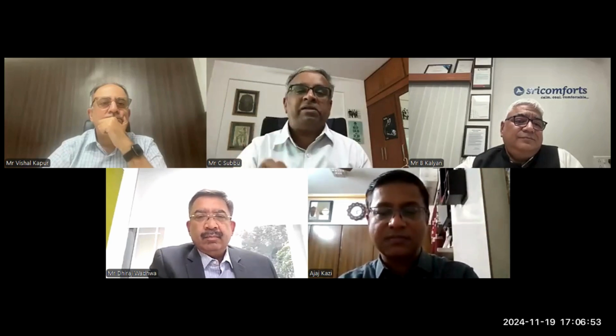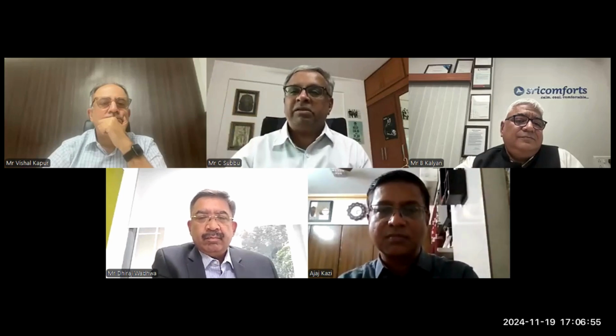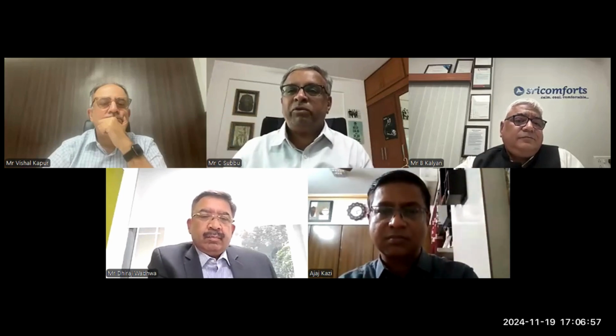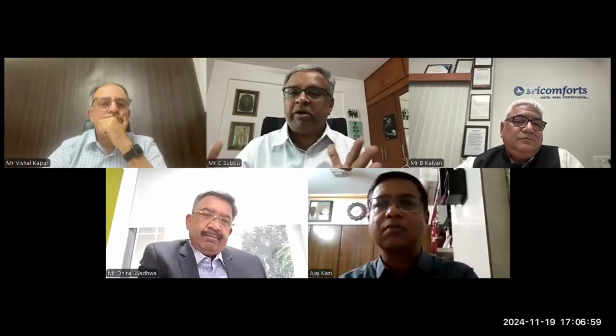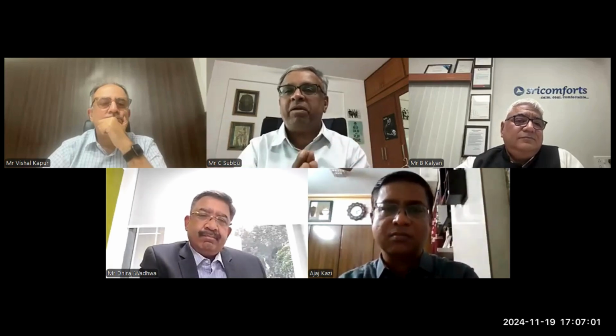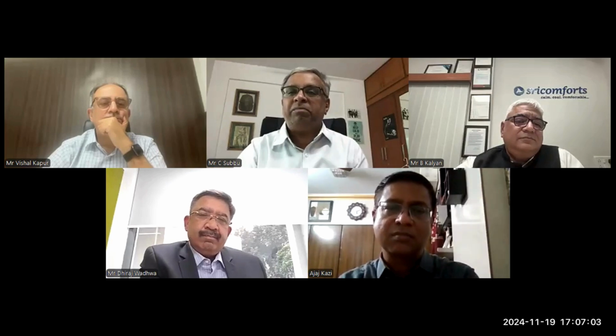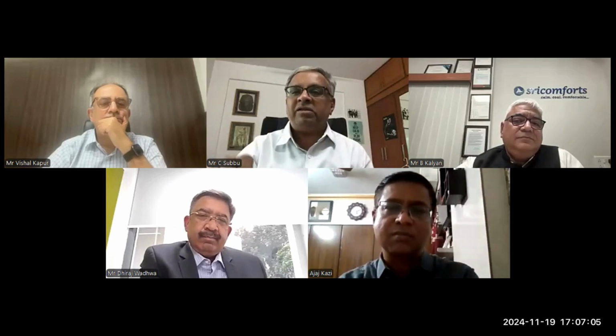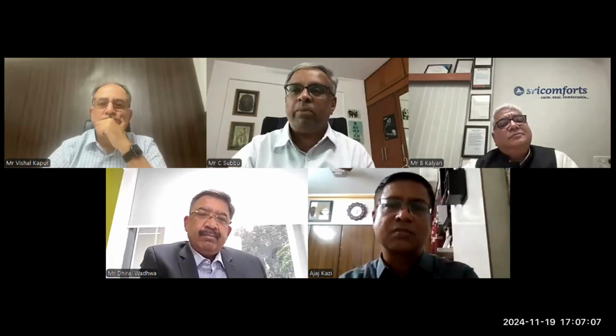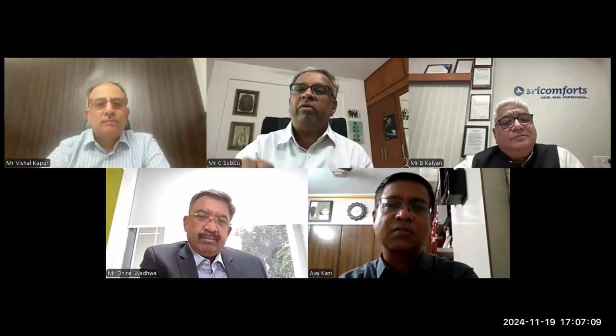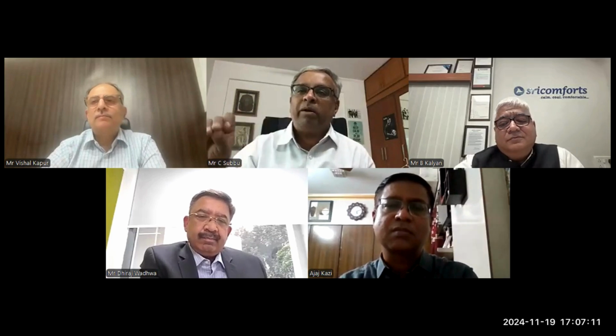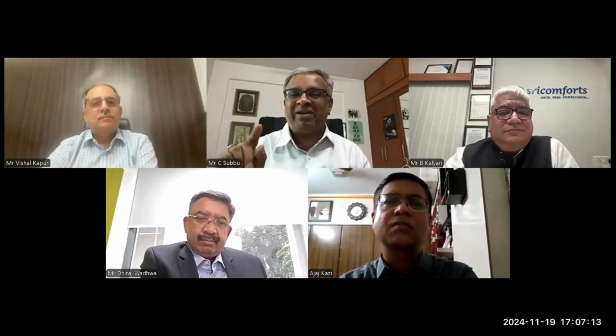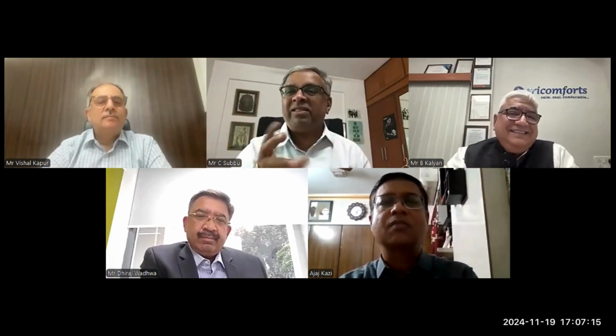Today what happens is somebody supplies the chiller, somebody supplies the AHU, somebody supplies the BMS. Who is tying them together, so that it all works as one system? Somebody has to tie it up. As Dheeraj said, integrated system efficiency, system kilowatt per ton, is what we want. But if everybody handles just their own equipment, who delivers the system kilowatt per ton? I think that's where the problem lies.